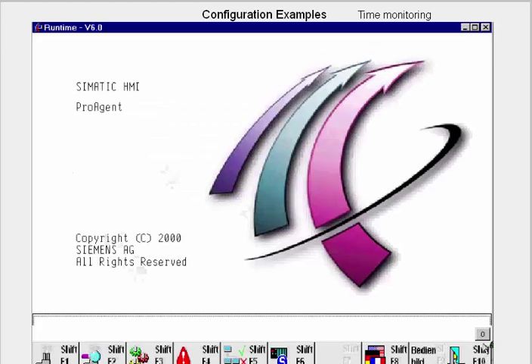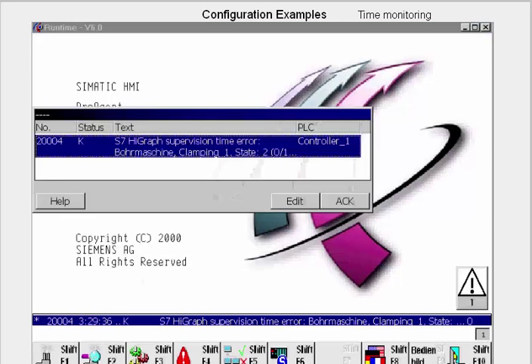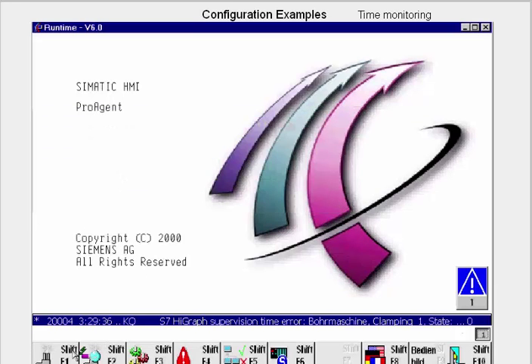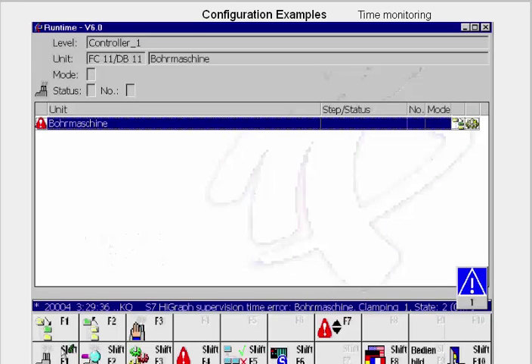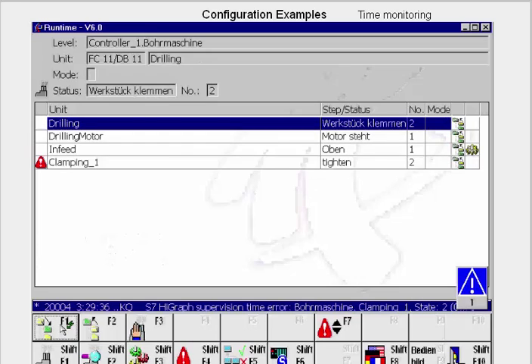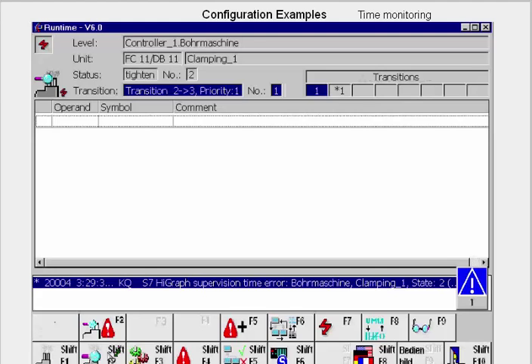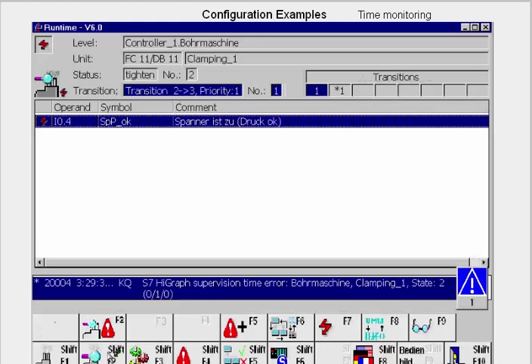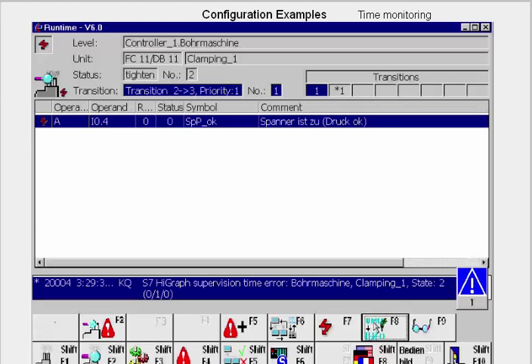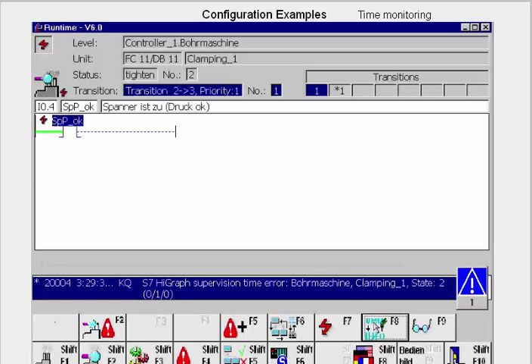Once a process fault has been triggered for which there is monitoring, a window is opened in which the state fault is announced. We acknowledge the message and switch to overview. There, we can identify the faulty unit and, by pressing the F1 button, the faulty subunit — here, the state graph Clamping Device. We change to detail view to see the addresses that caused the fault, plus the level, unit, state, and transition in which the fault occurred. With the F8 button, we can display the operations with which the addresses that caused the error are linked. If you click F8 again, you get the links displayed in Ladder.